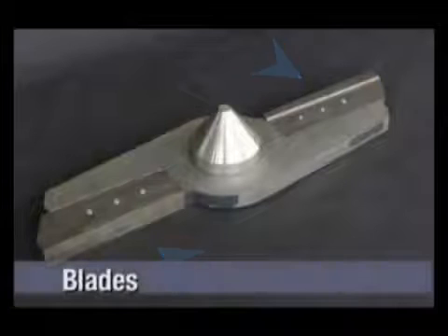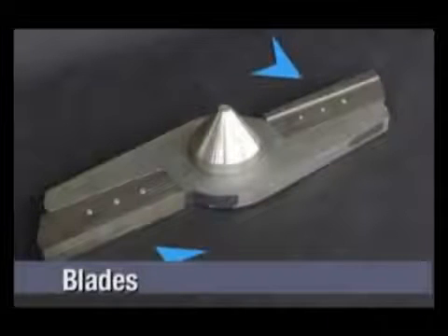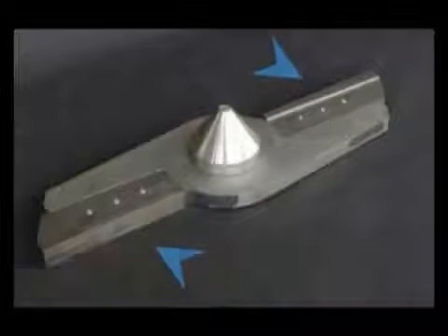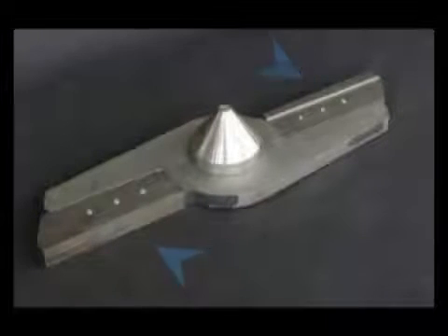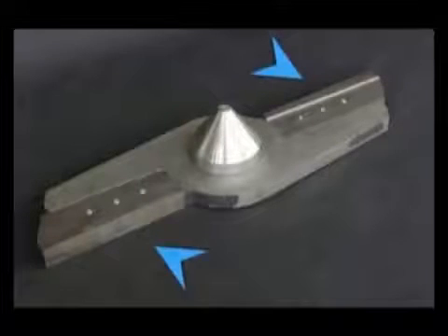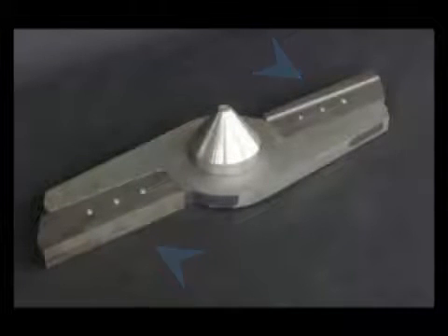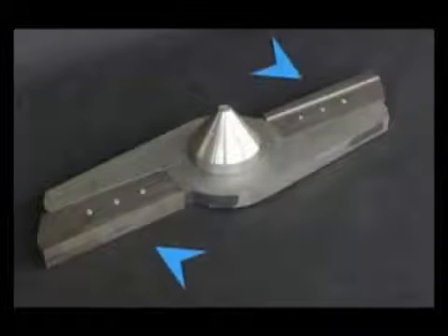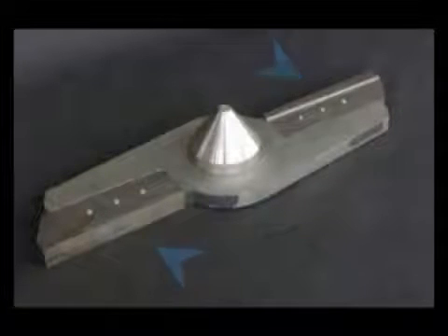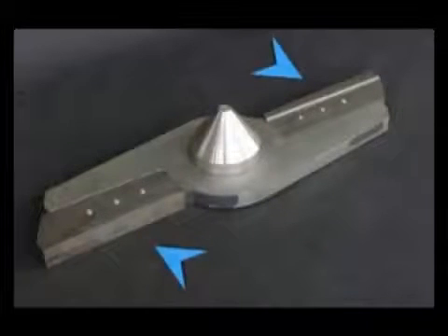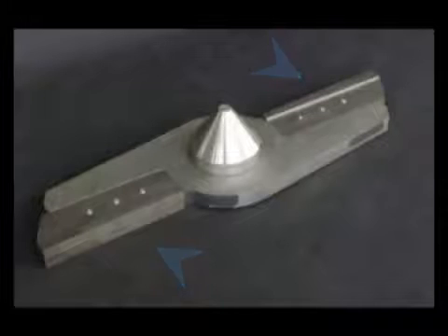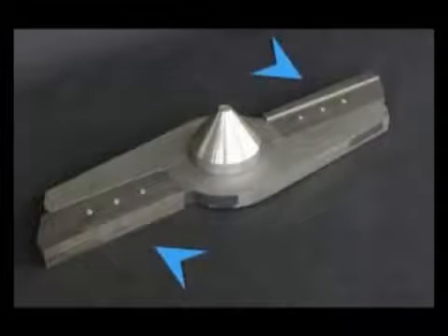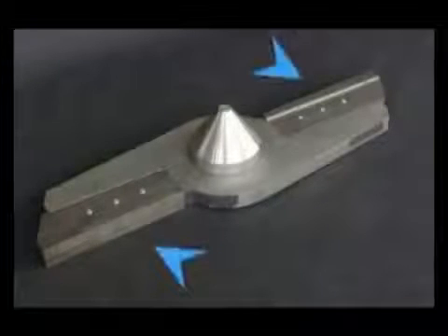The rise in temperature occurs through friction applied to the waste by rotary blades. The blades make contact with the waste and transfer their kinetic energy as heat. This action is made more effective by fixed blades placed on the sides of the sterilization cell.